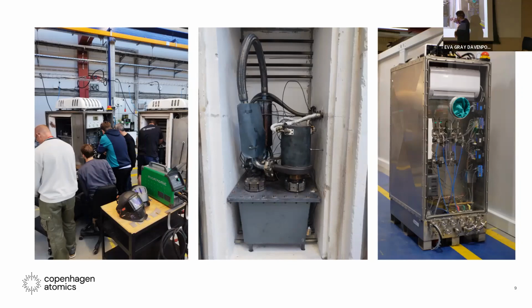We have wires going through for thermocouples and sensors, like leak detection sensors and gas. We put in a little pressure to prime the pump, then start it, and pump it basically around in a loop. Hence the name, it's just pumping around. Usually we pump at about 250 liters per minute, sometimes up to 300, which is about 80 gallons per minute. I'm not good at imperial, but yeah. It's just going at it in there, pumping around through a flow meter, a filter, then a valve, and back, completing that circuit.